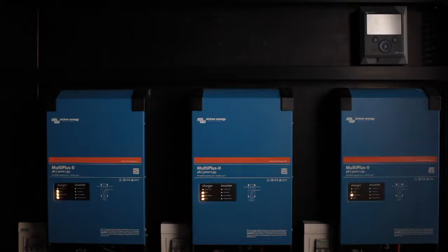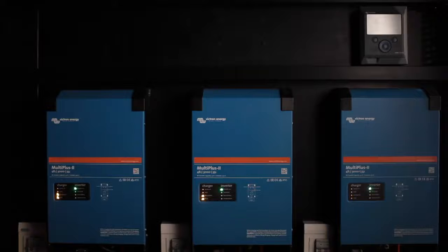Once the units have been connected together with the VE.Bus cable, they won't be producing 240 AC anymore. You'll see flashing lights on the front. The exact error light code may vary, but it'll look something like an alternating light, and the units won't be producing any power. To help demonstrate this, we've actually removed the MultiPlus-II GX and replaced it with just a regular MultiPlus-II. So we can now see the 3 units side by side as they are represented in the software.